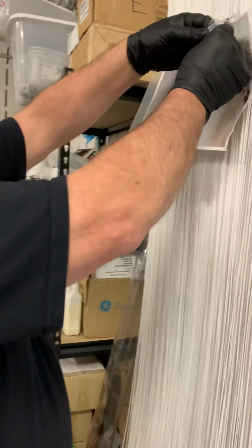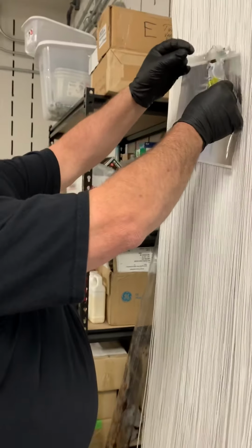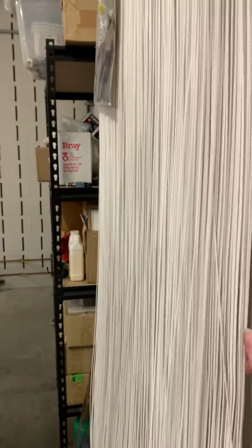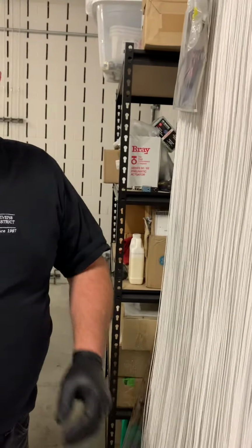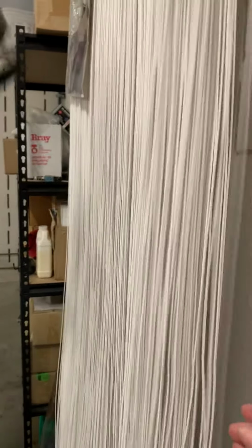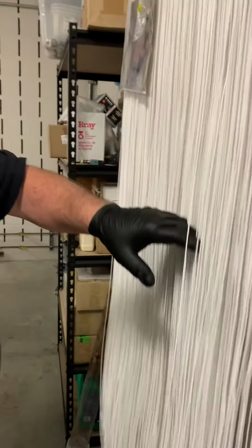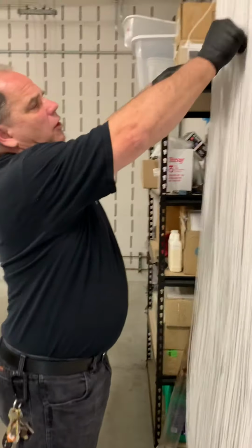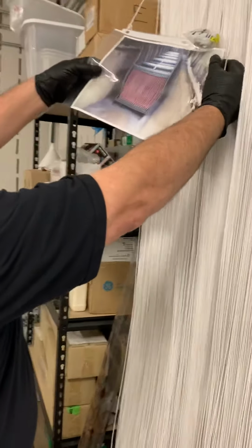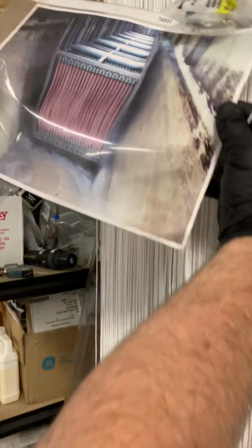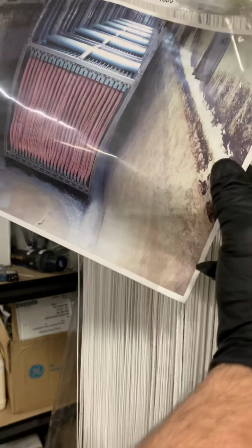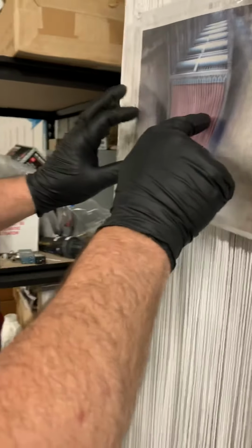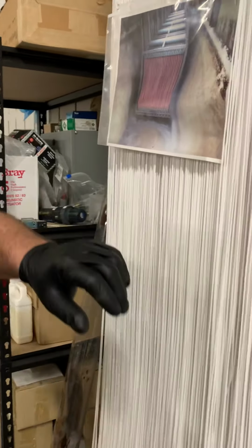Well, as you saw earlier, when you saw the aeration tanks, the bugs require food and air to do their thing. So these are the blowers that provide air for the wastewater process. Outside, you can't see them because they're deep in the tanks. There's a series of membrane cassettes, and they look like this. They're about the size of a Volkswagen, and there's 6 of them in each train, and there's 6 trains. Each cassette has 48 of these modules in it.